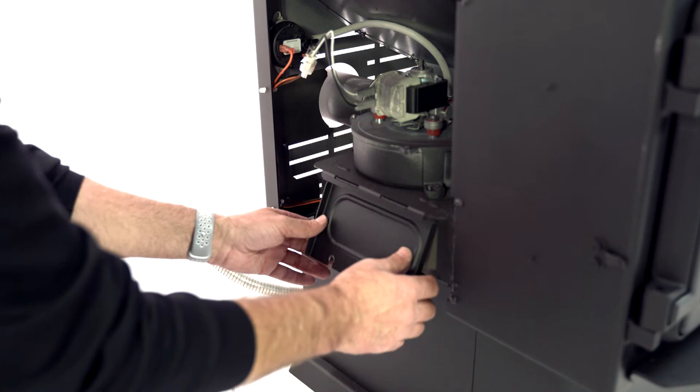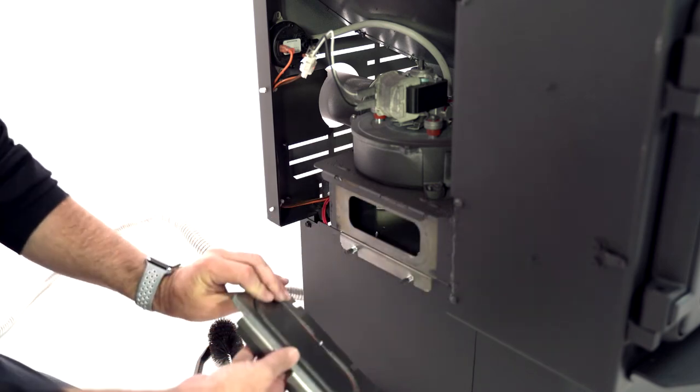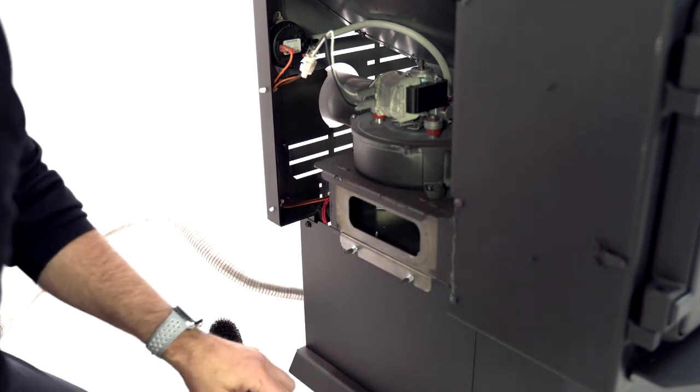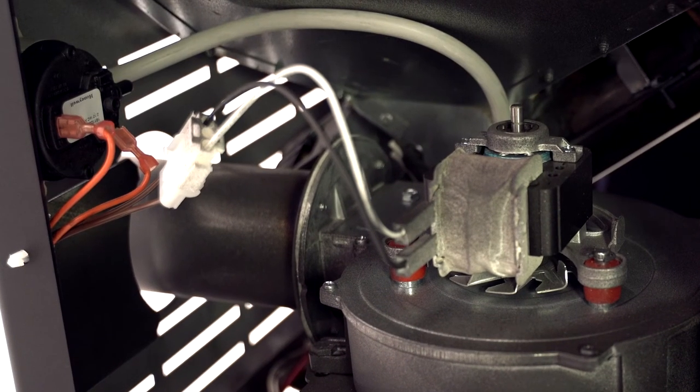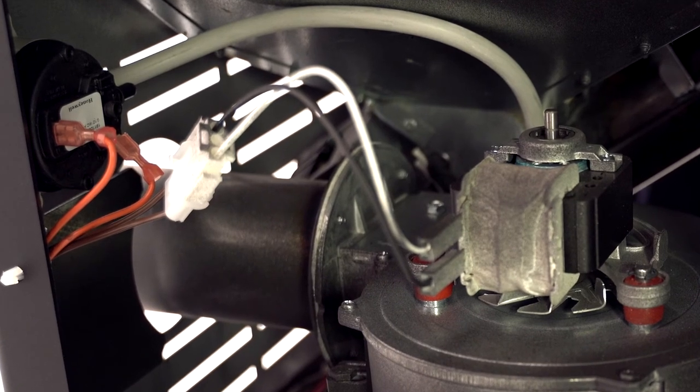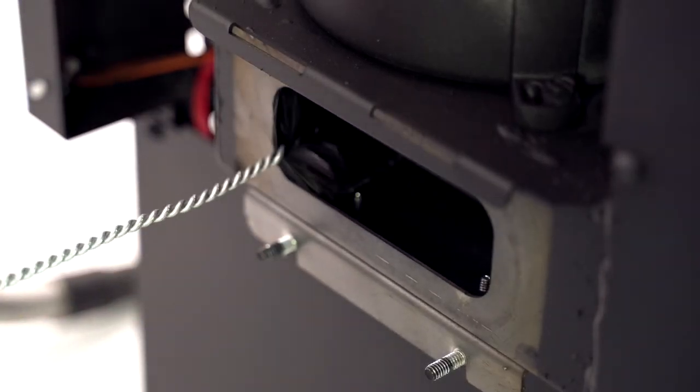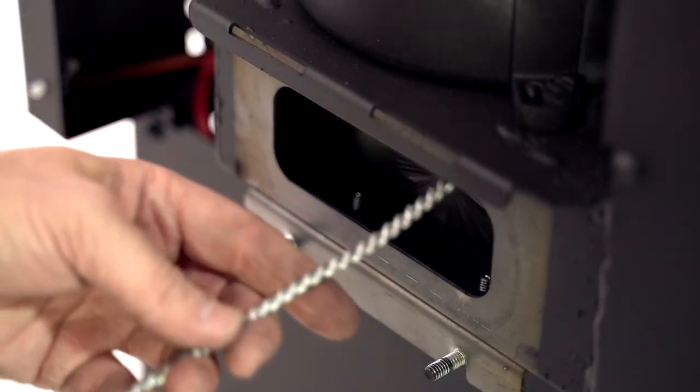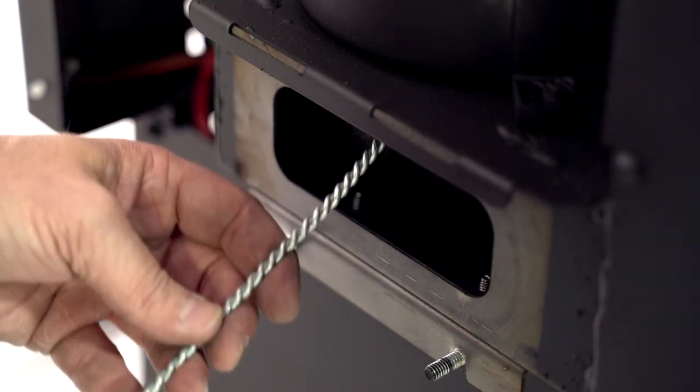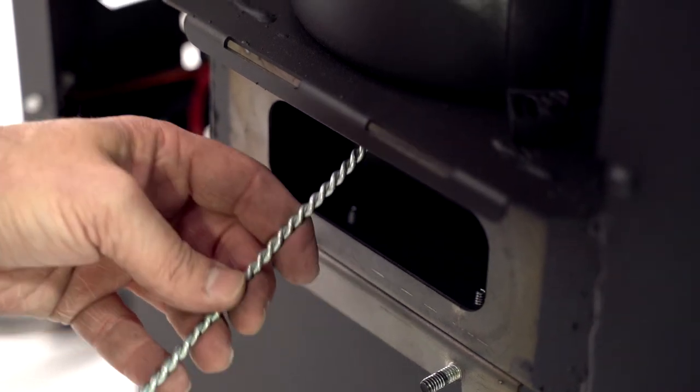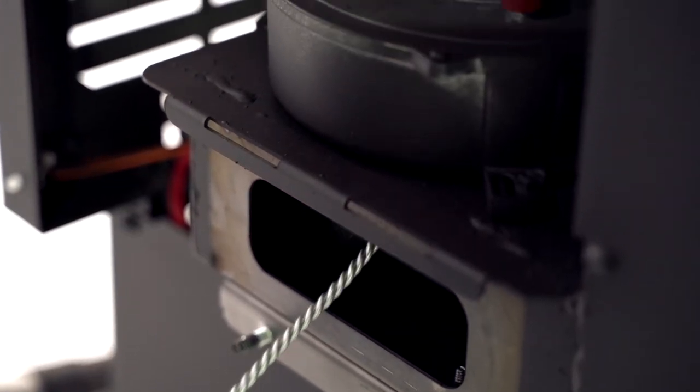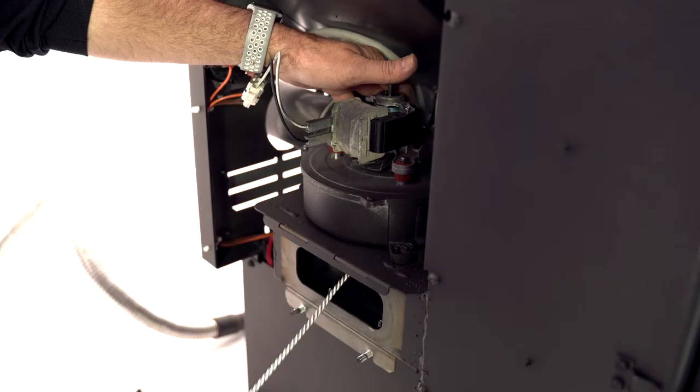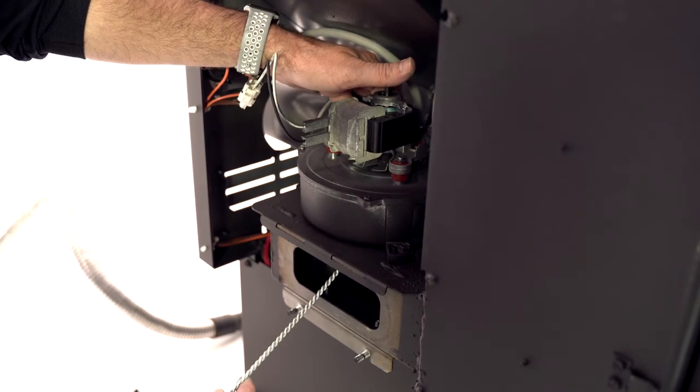Remove the bottom access cover and disconnect the pressure switch tube from the fan to prevent damage during maintenance. Clean the exhaust channel and the fan cage with a brush and a vacuum cleaner. Delicately clean the fan blades to prevent them from becoming unbalanced, which would affect the motor.